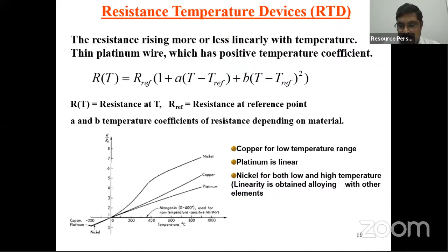So the RTD has a wide operating range, as I already mentioned. It can be used between -252 and about 1000 degrees Celsius. It is highly sensitive and much better than the thermocouple. Accuracy is also good, plus or minus even 0.05 degrees Celsius, which is highly impossible in the case of the thermocouple or thermistor. And for reliability and repeatability, even if you use it for about 10 to 15 years, its characteristics are not going to change.